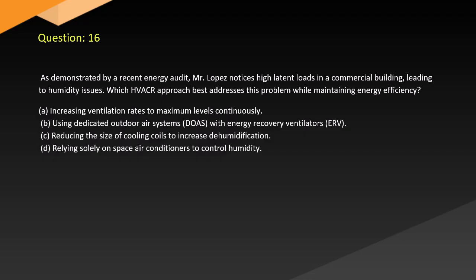Question 16. As demonstrated by a recent energy audit, Mr. Lopez notices high latent loads in a commercial building, leading to humidity issues. Which HVACR approach best addresses this problem while maintaining energy efficiency? A. Increasing ventilation rates to maximum levels continuously. B. Using dedicated outdoor air systems, DOAS, with energy recovery ventilators. C. Reducing the size of cooling coils to increase dehumidification. D. Relying solely on space air conditioners to control humidity.